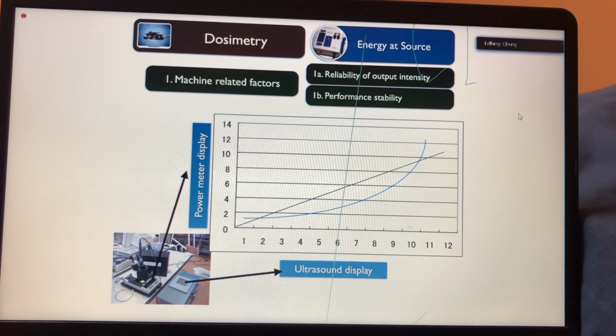And also the manufacturers, when they calibrate for you, you don't know what they're doing. Sometimes they just calibrate lowest intensity, highest intensity, and they draw a line in between that. When actually we know that's not true. It's not linear, it's curvilinear. So you need more data points to get the calibration. And the video I was about to show you actually shows you that it can be done in less than 5 minutes. And anybody can do that in 5 minutes.